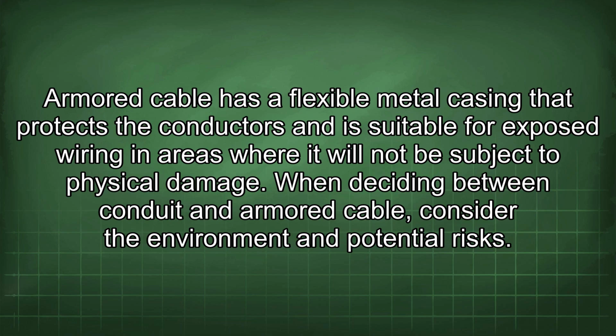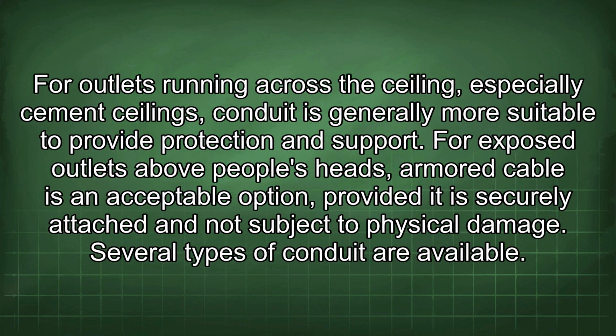When deciding between conduit and armored cable, consider the environment and potential risks. For outlets running across the ceiling, especially cement ceilings, conduit is generally more suitable to provide protection and support. For exposed outlets above people's heads, armored cable is an acceptable option, provided it is securely attached and not subject to physical damage. Several types of conduit are available.